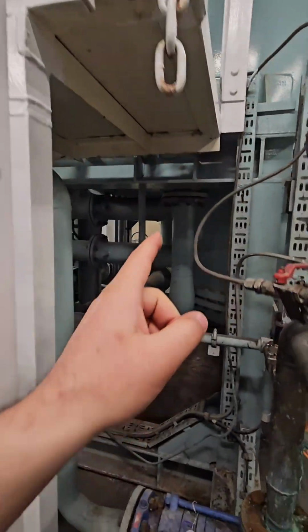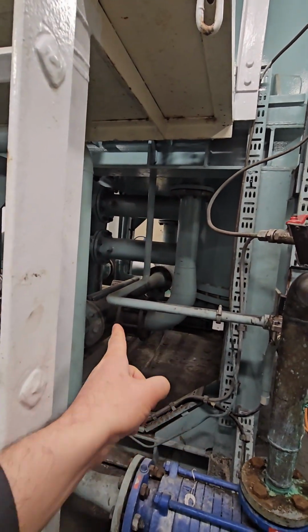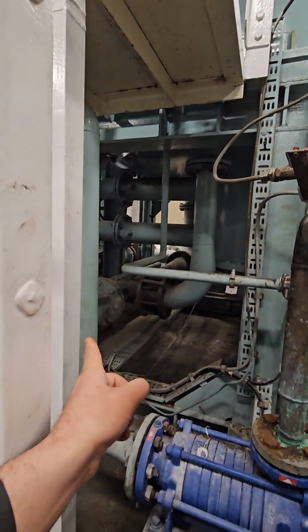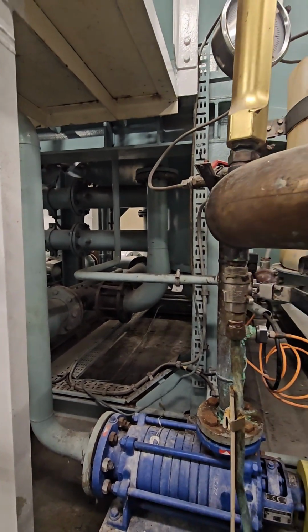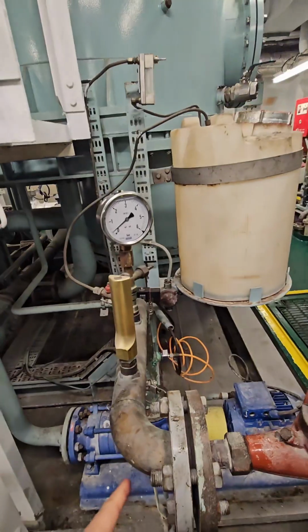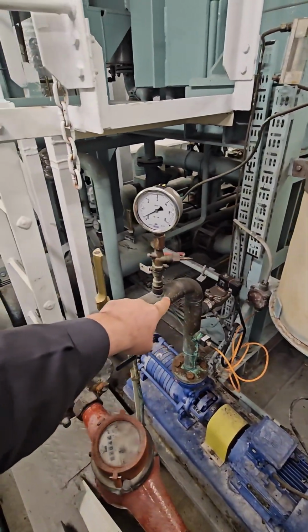Back to the distillate pump, it's mounted low to get good suction from the condensed water level. It pumps the fresh water out reliably, usually at 2 to 5 cubic meters per hour depending on the unit size, and includes safeguards like a salinometer to monitor quality and prevent high salinity water from entering the tanks.